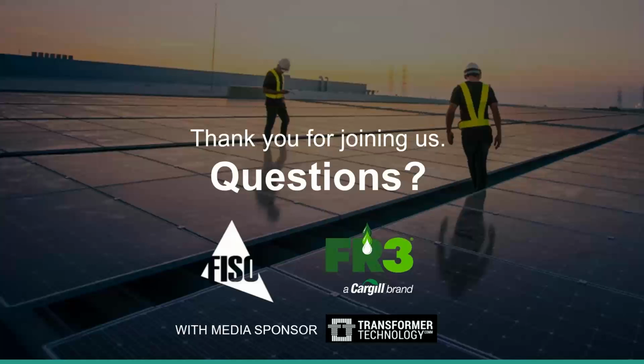Okay, so maybe Peter, regarding fiber optics, does it make sense to equip distribution transformers, so smaller transformers, with fiber optic sensors? Well, if you would ask me this question 10, 15 years back, I would say not really. But nowadays, a small distribution transformer can become more critical than a grid transformer. So distribution transformers with a lot of consumers, which are not only consumers, but also now producers of energy, are much more overloaded.